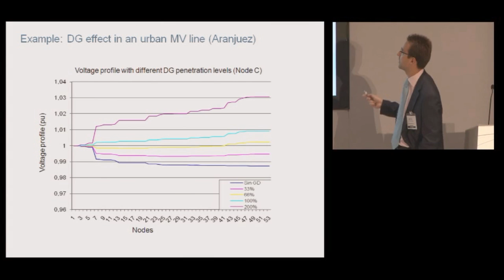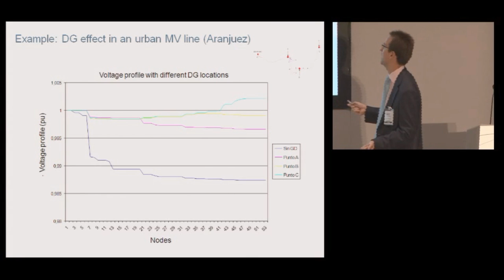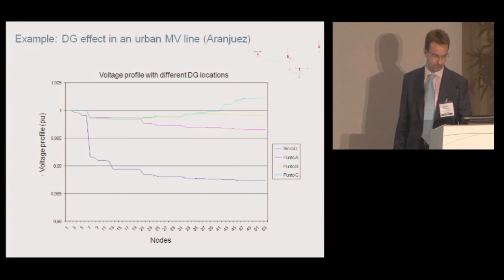If we compare the impact in terms of where the distributed generation is located, the farther the distributed generation is located in the medium voltage grid, the worse the impact on the voltage control in the medium voltage grid. And you can see this example. At point C, the blue line, the effect is to increase the voltage much more than if we are connecting, for example, at point A, where there is less variation, comparing with no distributed generation connection.